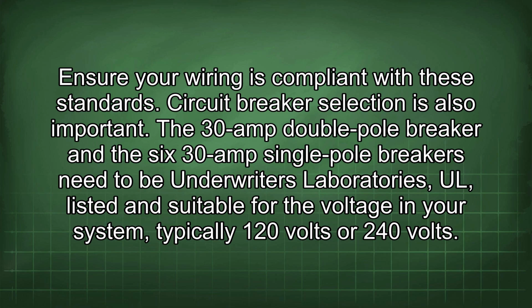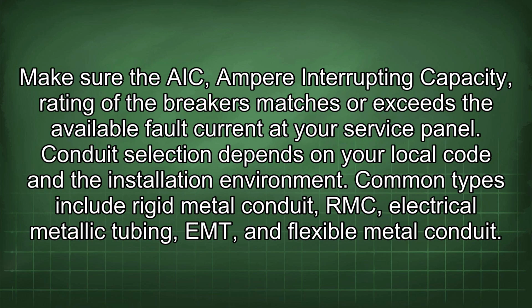Circuit breaker selection is also important. The 30-amp double-pole breaker and the 6 30-amp single-pole breakers need to be Underwriters Laboratories, UL, listed and suitable for the voltage in your system, typically 120 volts or 240 volts. Make sure the AIC, ampere interrupting capacity, rating of the breakers matches or exceeds the available fault current at your service panel.